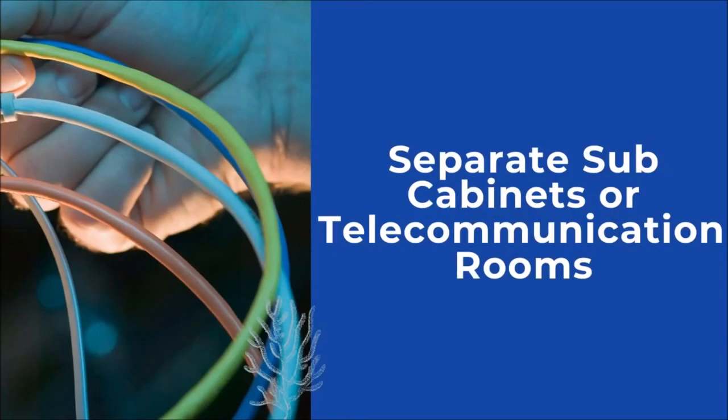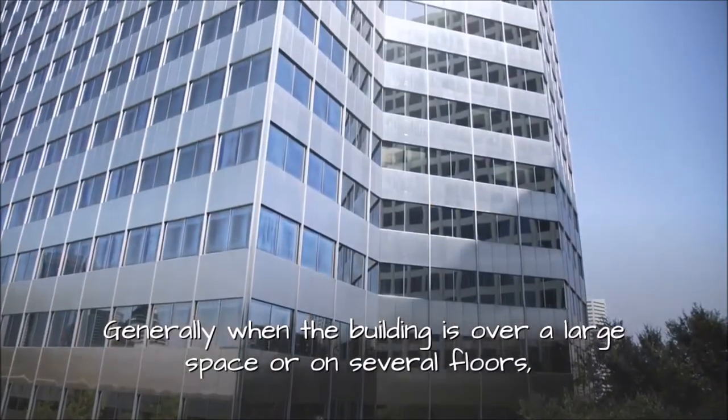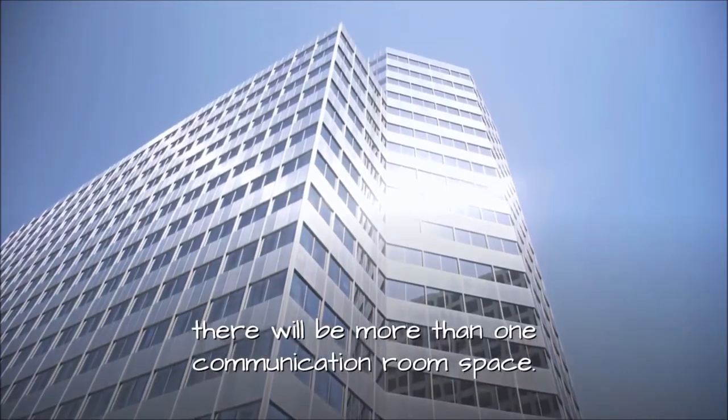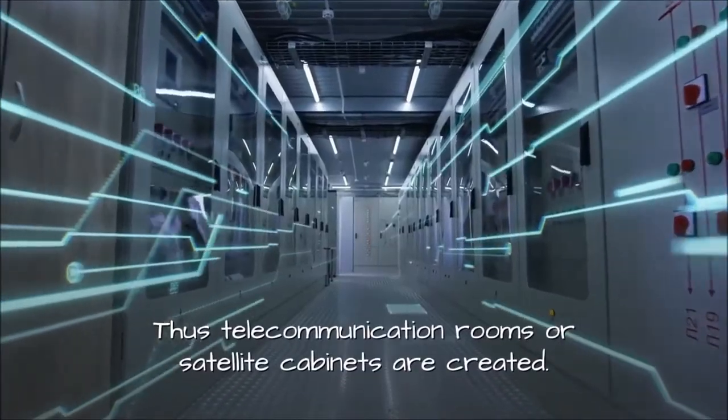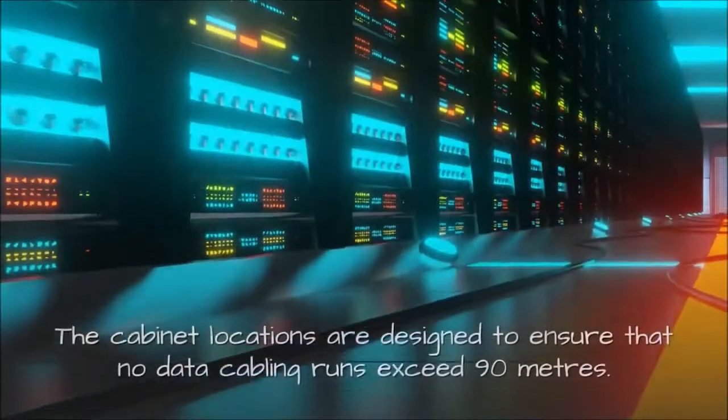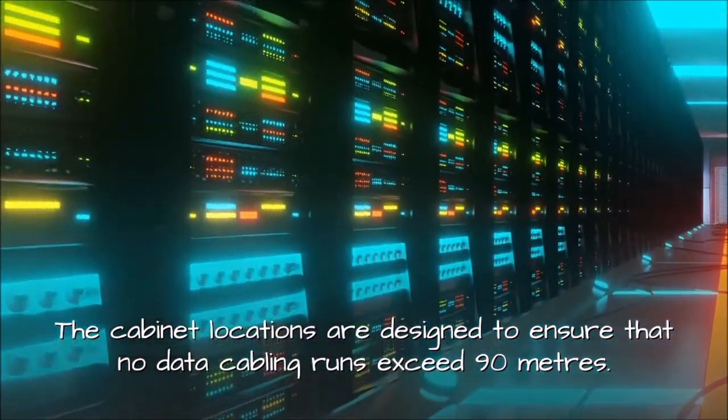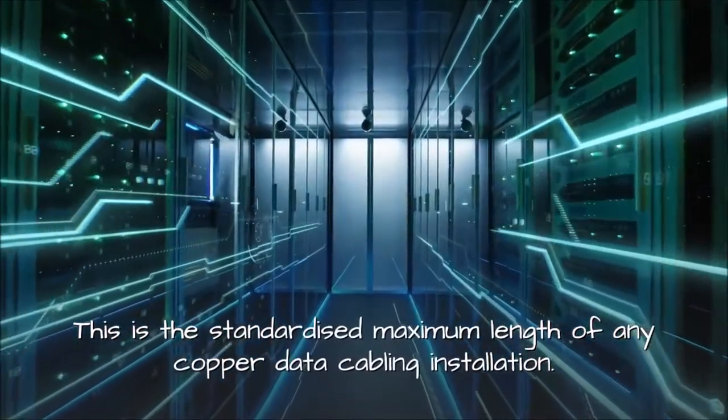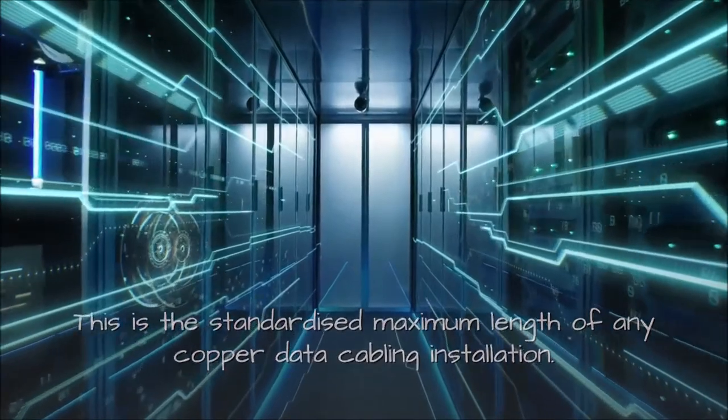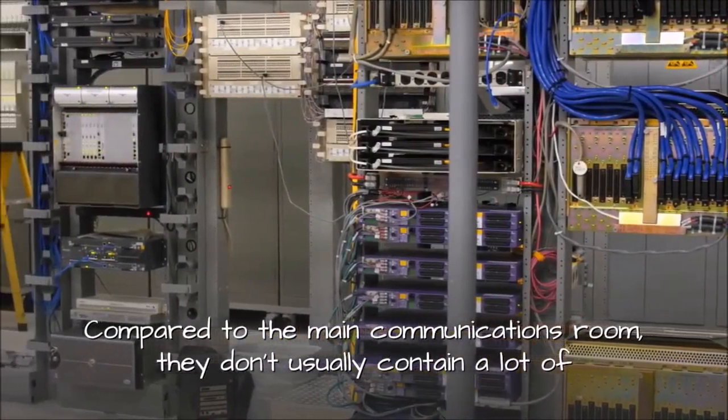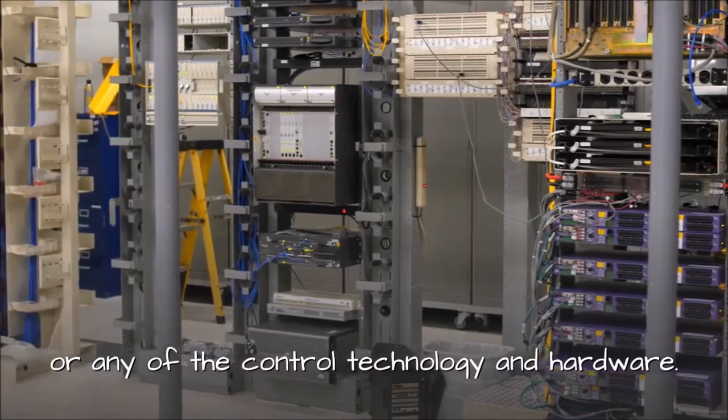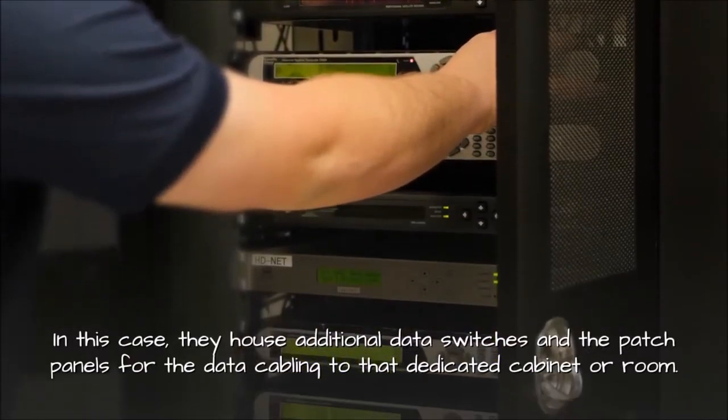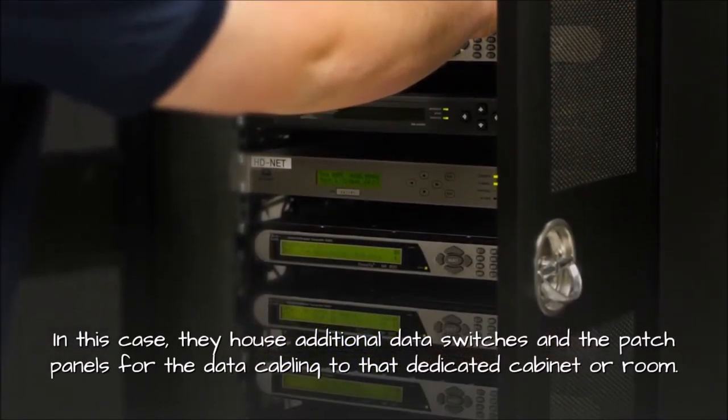Separate sub-cabinets or telecommunication rooms. Generally when the building is over a large space or on several floors, there will be more than one communication room space. Thus telecommunication rooms or satellite cabinets are created. The cabinet locations are designed to ensure that no data cabling runs exceed 90 meters. This is the standardized maximum length of any copper data cabling installation. Compared to the main communications room, they don't usually contain a lot of or any of the control technology and hardware. In this case, they house additional data switches and the patch panels for the data cabling to that dedicated cabinet or room.